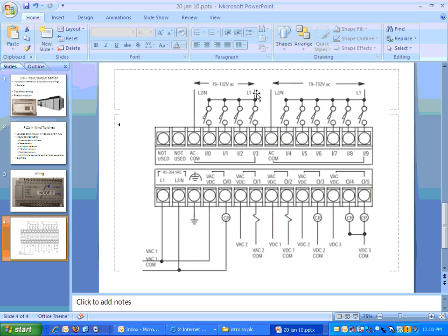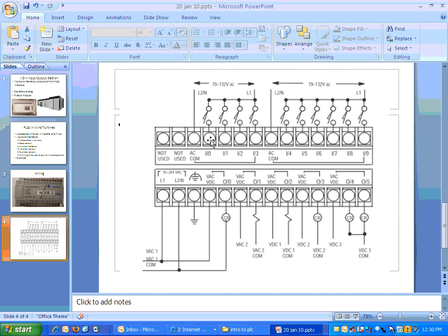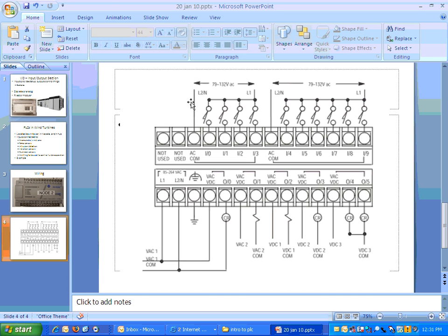Job two is to connect an input. To connect an input, you can see from the diagram, L1, and here they're showing four switches all connected to these four inputs. These inputs are numbered from zero through three. In these devices, zero counts. We're used to ignoring zero, but input zero is the first input. So you would hook, in order to connect a switch, you would connect one side of the switch to hot, or L1. The other side of the switch to whichever input you're going to use. And then the common lead, which is going to go back to neutral, is connected here. This is your L2.